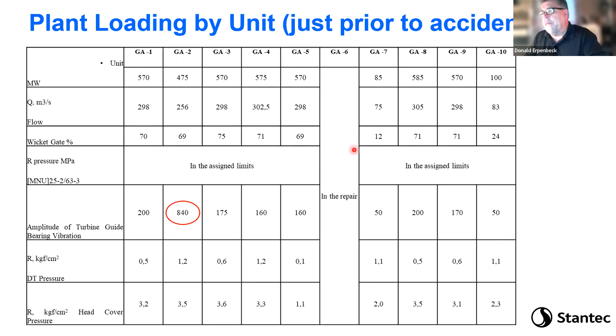Another interesting thing going on that no one has been able to explain yet is that the megawatts were at 475, but yet the wicket gates, which control how much water goes into the turbine, were 69% open. Look at unit 1, it was 70% open, but at 570 megawatts. And the same thing on unit 5, and even unit 4 at 71, 575. So you can kind of see something else was going on as well, and some of that's not fully explained.